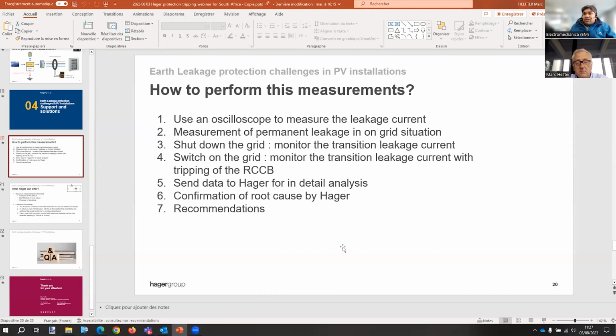Reagan is asking, will there be generic sizes depending on the size of the inverters? It might be difficult to design per leakage size. I guess we can find one solution that works in most situations, so we don't need to have a big range of filters. Normally, one filter should do the job for all situations. Of course, if it's very big industrial installations, it's different. But here we are speaking of residential, maybe small commercial buildings, and then I guess it should be quite easy to do. Okay. This answers your question, Reagan. Perfect.